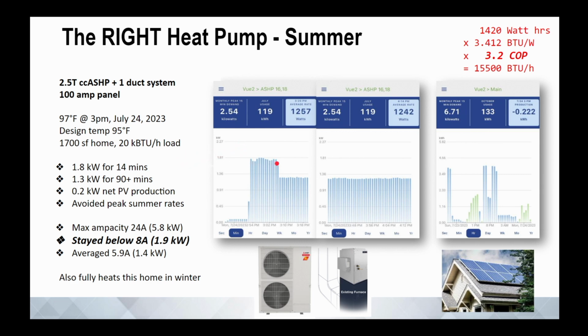And it runs for 14 minutes at 1.8 kW, or 15 minutes. And then it steps back, and then it runs at 1.3 kW for an hour and a half. It's because it was off before that. It steps up, sort of cools the system, cools off the ductwork, cools the refrigerant inside, and then it settles back and runs for 90 minutes at a little bit lower rate. And over an hour and a half, peak rates on Xcel's system, this undersized PV system, because of just limitations on the roof and trees and all that stuff, is still big enough to cover the cooling load and a little bit of operational stuff, the fridge, maybe something in pumps or whatever going on. And so we're still net positive production for that time frame to the tune of 200 watt hours, right?